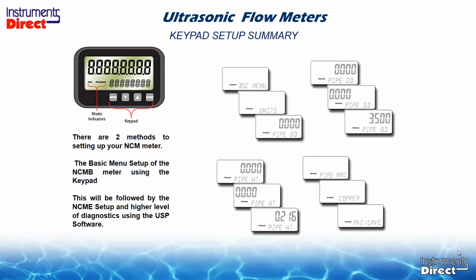So is it hard to set up this kind of flow meter? The answer is no, even I can do it. All you need is some basic application data, such as the pipe material, the pipe OD, the pipe ID or wall thickness, and the type of liquid, which in most cases is water. With this information, we can program the NCM model by using the keypad.